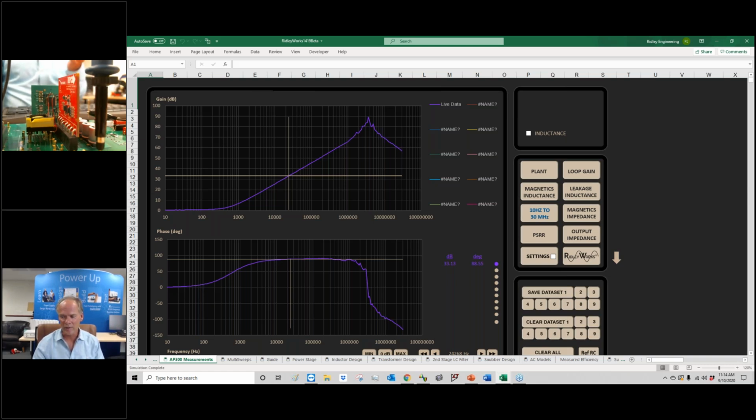So if you're military, aerospace, you need rigid rules on calibration, you need mil specs, it's the AP310. It's still, you know, the Cadillac of the industry, or the Ferrari or whatever. It's got high power output, it's got the bigger frequency range, it's got very low frequency operation. The AP does it better than anything, and we tie that into our software the same way.